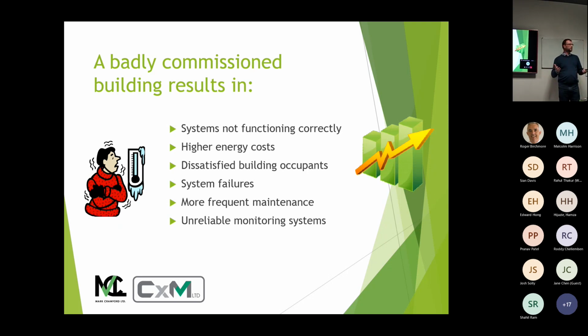So if you've got a pump that's running flat out at 50 hertz, or a fan that's now running way above 50 hertz as the systems allow them to now with the VSDs - it doesn't need to, because the system's not been commissioned correctly, but it's easy just to ramp the fan up and just let it get on with it. That's not going to last as long as a well-commissioned system, a well-commissioned bit of plant. Therefore, it's going to be replaced more often. Therefore, there's more costs. Therefore, the OPEX values of the building go up, and it's a rolling domino effect.